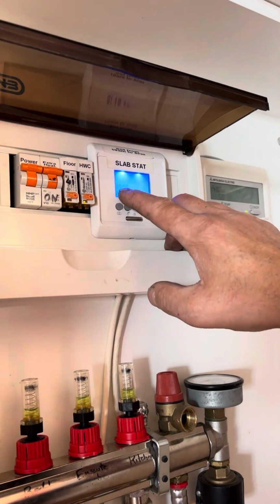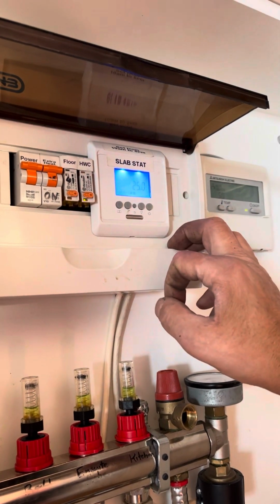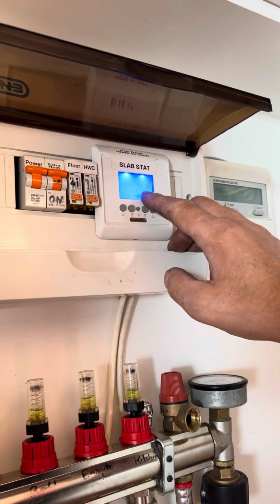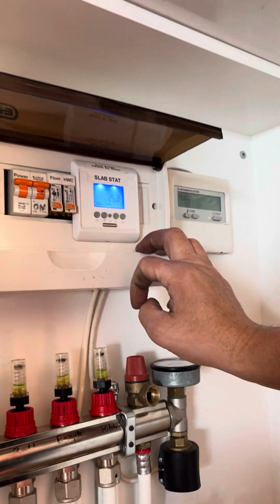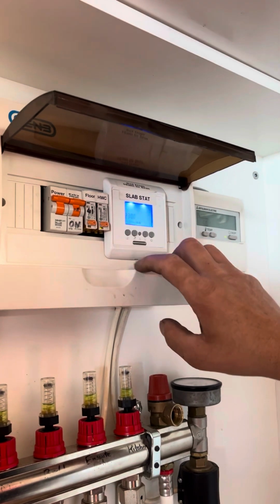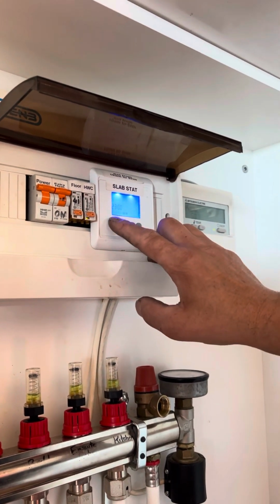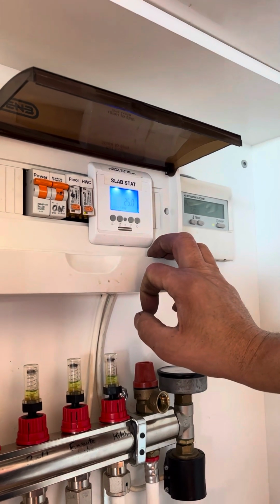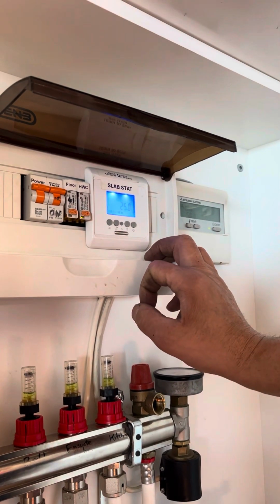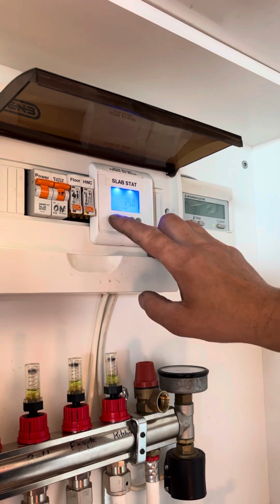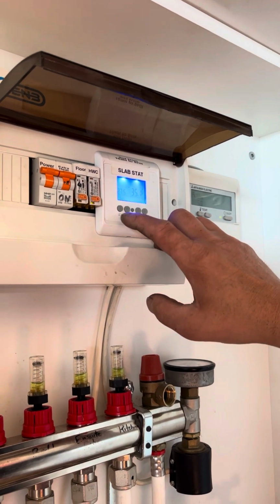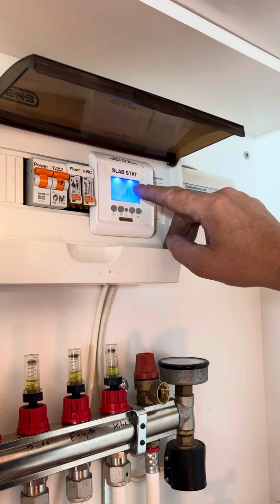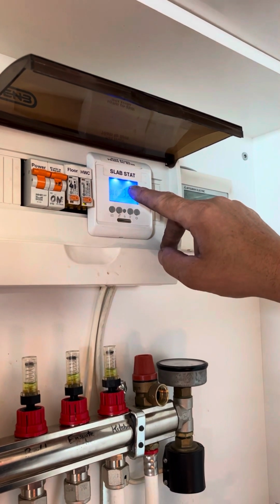And then at 1900, this is when your solar's gone, it steps back to 25 degrees, which is your base temperature. And then the last one is 2300 at night, which is 25 as well. So you've got a base temperature of 25 degrees and you've got a maximum temperature of 30. Right, so we push that again, it gets you back to your normal screen, and then we push it again to make sure we've got it on clock, which is the setting.